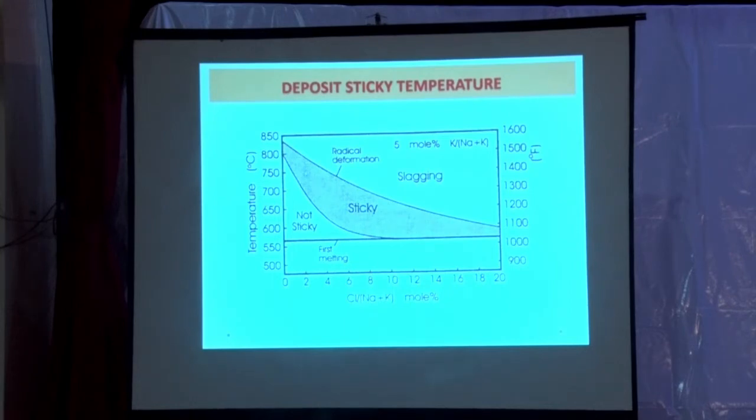So it shows here that the flue gas at 750 degrees centigrade, when it was going through without any sticky deposits, at an ideal level, will start depositing at this lower temperature. You can see the huge impact. And when it goes to 4, when it goes to 6, and normally most of the mills are having 10, 12, 14, an enrichment factor we have tested in so many mills, you see it has come down to 560 degrees.